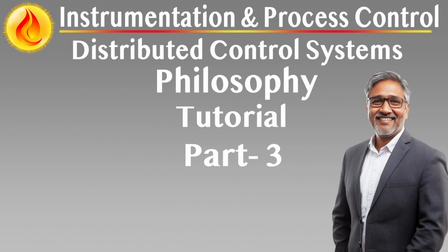System outputs and actuation. Hardwired fail-safe outputs. FGS outputs for critical actions, e.g. deluge actuation, damper closure, ESD interlocks, are hardwired directly to the actuating elements. All outputs are designed to de-energize to trip state under failure or detection. Pulse-tested field devices. Outputs to actuators are pulse-tested for coil integrity, wiring continuity, and load resistance. Results are logged and trigger maintenance alerts upon fault detection.